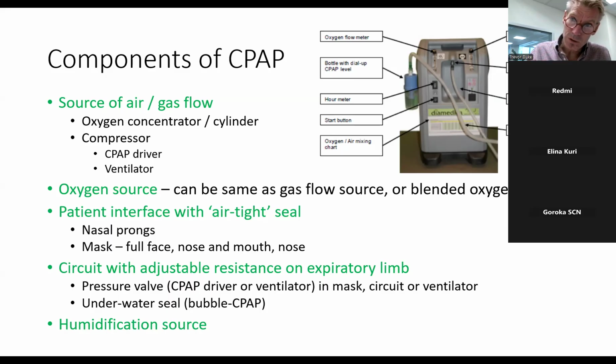It goes into a bottle that is filled with water, and the distance that the tubing is underneath the water is the amount of CPAP that will be given. So if it's 5 centimeters underneath the surface of the water in the bottle, then it will be 5 centimeters of water of CPAP. Most children are on somewhere between 5 and 10 centimeters of water of CPAP. And that means that the tubing, the distal end of the expiratory limb, is 5 or 10 centimeters underneath the water. And that's what generates the CPAP effect, coming from the expiratory limb.